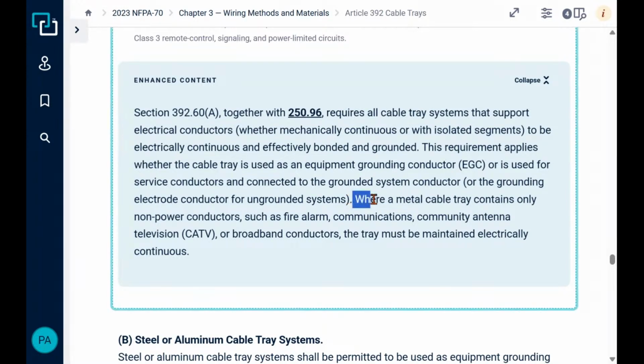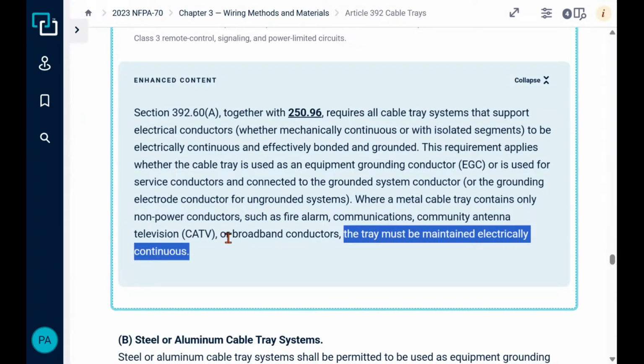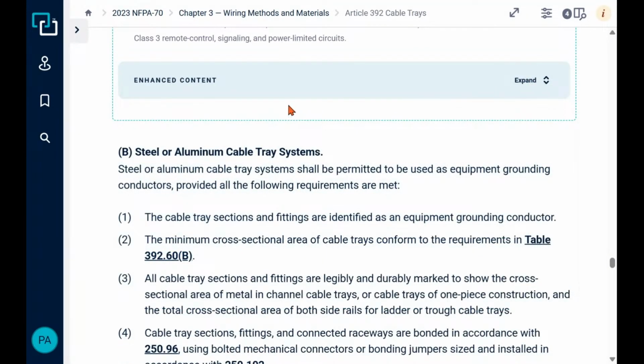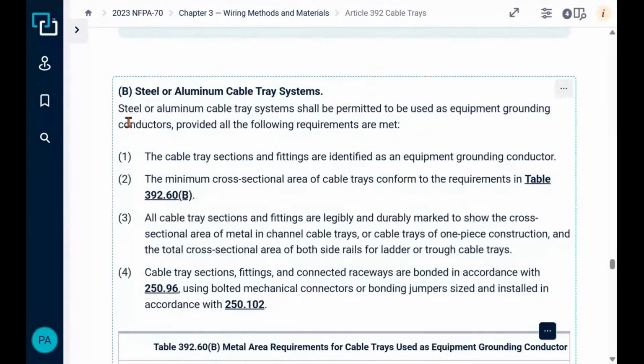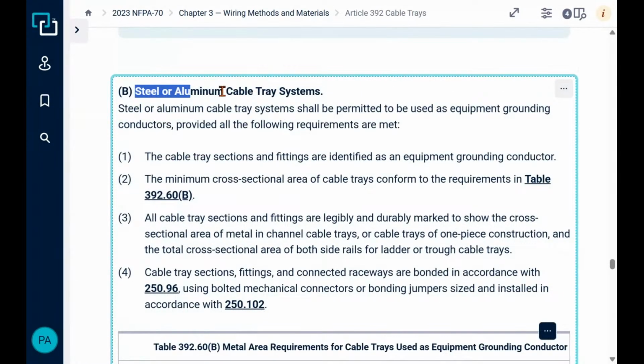Now see, for example, it says where metal cable trays only contain non-power conductors such as fire alarm, communication, CATV, and broadband, the tray must be maintained electrically continuous. So that's going to mean it's either one long continuous run or you're going to have bonding jumpers that connect it. Now you're probably saying, well, isn't that the same for power as well? Then you get down here to the additional requirements for steel and aluminum cable tray systems, and it gives you the rules where it tells you they shall be permitted to be used as equipment ground, provided they meet all the following requirements.